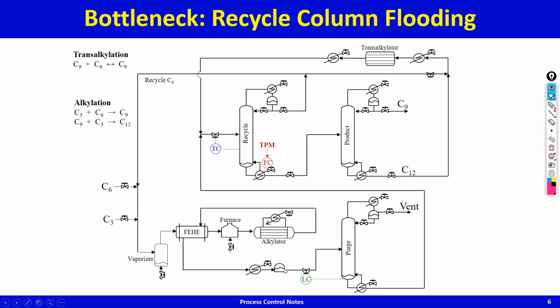And by the way, it seems like a long loop, but it's not a long loop, in the sense that the moment you increase vaporization rate, pressure will increase. The moment pressure increases, this fast pressure controller on the condenser, or on the flash drum cooler, will increase the cooling duty, and if the cooling duty increases, the condensation rate increases, and as the condensation rate increases, the level will start going back up. So this level controller is not a long loop.